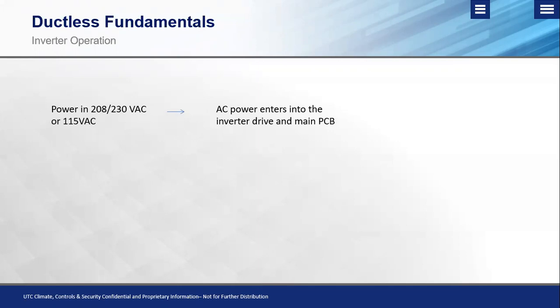Now, inside of that ductless unit, we're going to be using AC and DC power. That DC power is derived by taking the AC voltage and running it through what we call a rectifier, or rectifying AC voltage to DC voltage. And that is achieved by using a diode. A diode essentially is like an electrical check valve. That electrical check valve allows voltage to pass through, but not back, achieving the AC to DC conversion. Now, in ductless systems, we use AC and DC voltage, as we're all aware now: AC voltage for things such as crankcase and base pan heaters, DC voltage for things such as the compressor, outdoor fan motor, and reference signals from thermistors to be able to tell the unit what it needs to do.